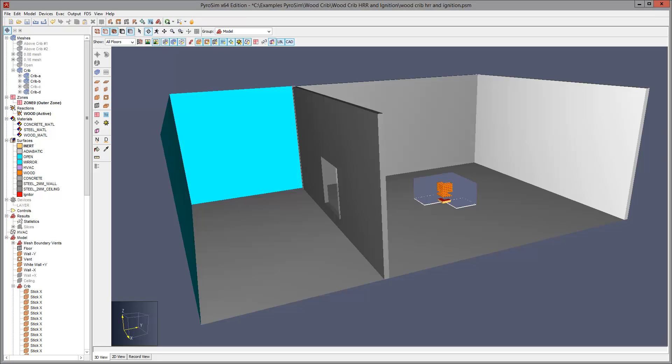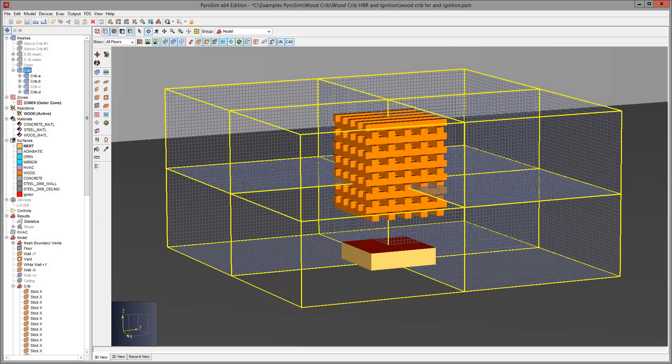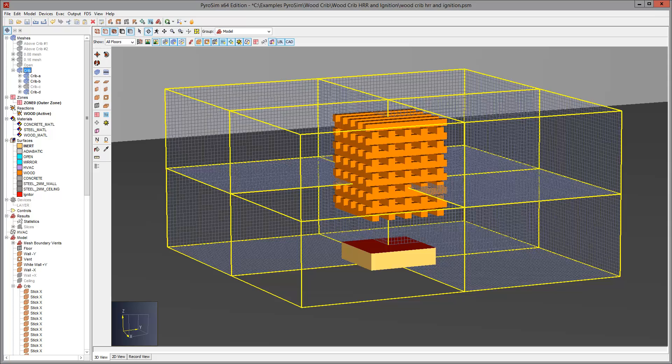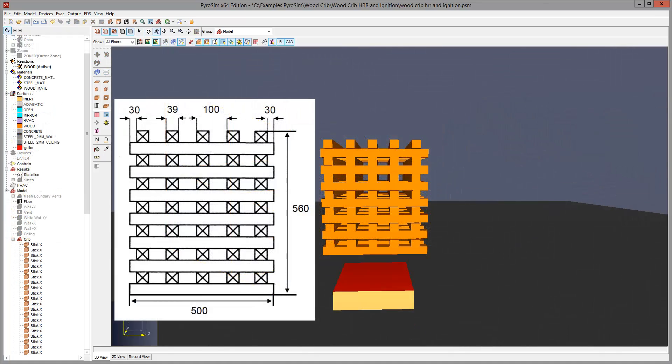We use the same building model that we used in previous calculations. If you use burn away, you should model a fairly accurate approximation to the true crib geometry. Otherwise, you cannot capture the ignition and surface burn rate of the sticks accurately.